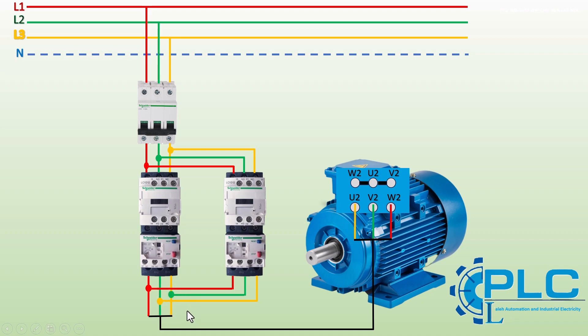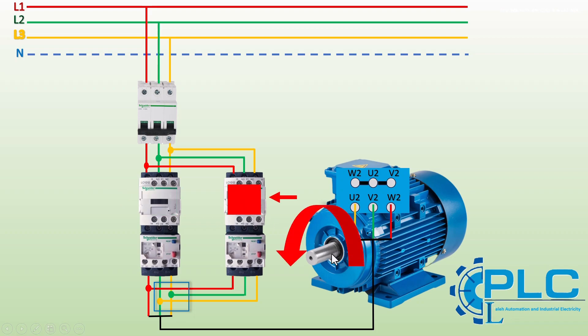In this case, I swapped phase two and phase three at the contactor's output. With this setup, when contactor one is active, the motor will run in the forward direction. When contactor two is active, the motor will run in the reverse direction, because we swapped the two phases.